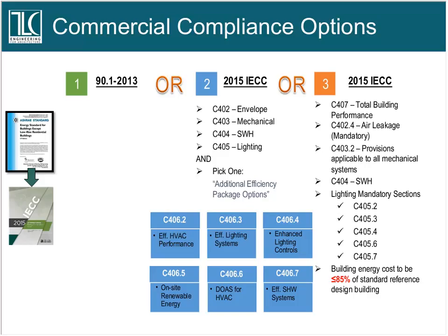I'll tell you that in my experience, one of the deal killers for following ASHRAE 90.1 2013 is a mandatory requirement that, for receptacles in office spaces and computer labs, at least half of those receptacles be on some sort of scheduling program, either through occupancy or tied to another system, like a building alarm system, that cuts power to those receptacles when the building is scheduled to be unoccupied. And a lot of building owners have a real problem with that. So that tends to be a deal killer for ASHRAE 90.1. That requirement does not exist yet in the international code versions.